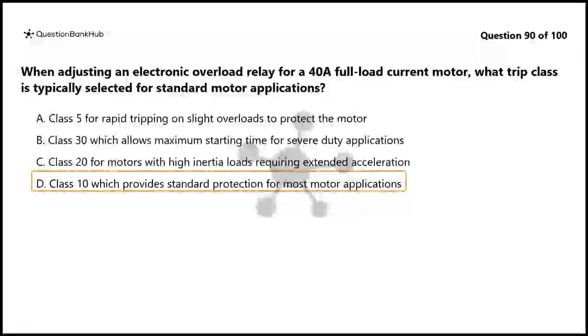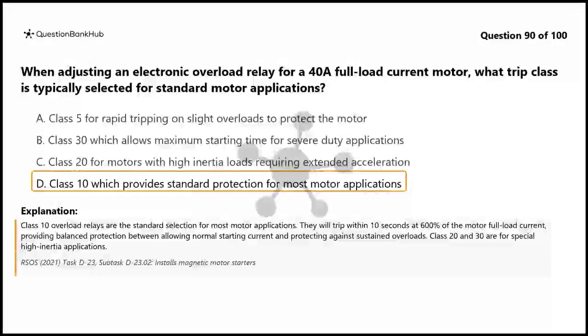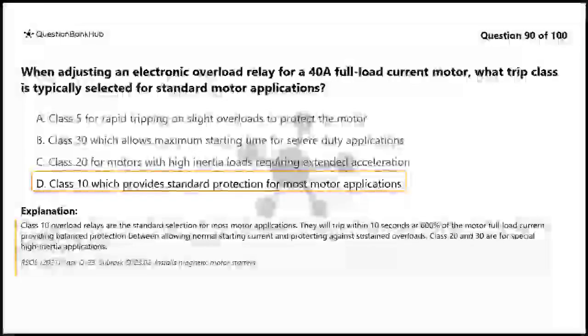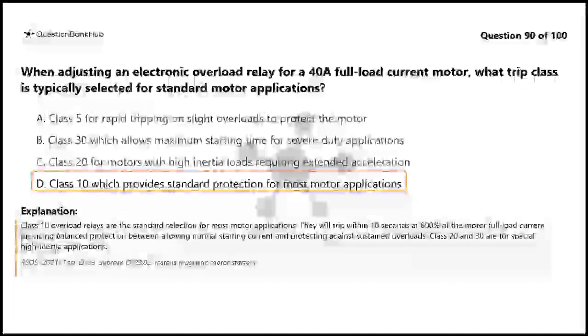The correct answer is D, Class 10 which provides standard protection for most motor applications. Class 10 overload relays are the standard selection for most motor applications. They will trip within 10 seconds at 600% of the motor full load current, providing balanced protection between allowing normal starting current and protecting against sustained overloads. Class 20 and 30 are for special high inertia applications.